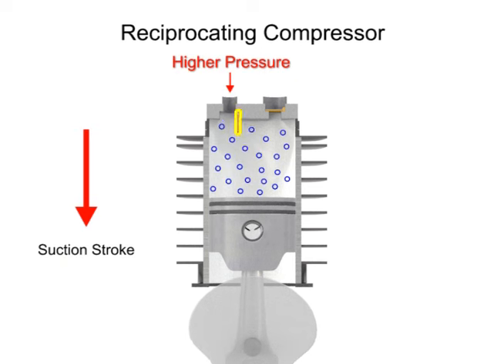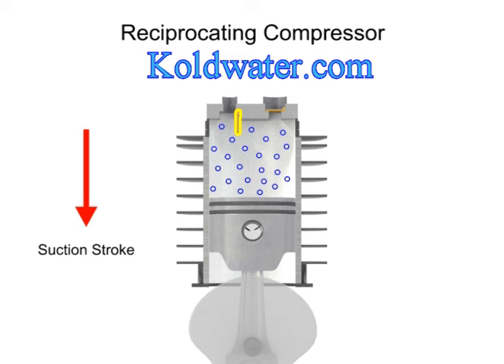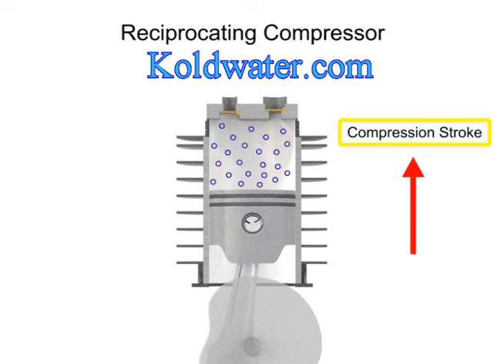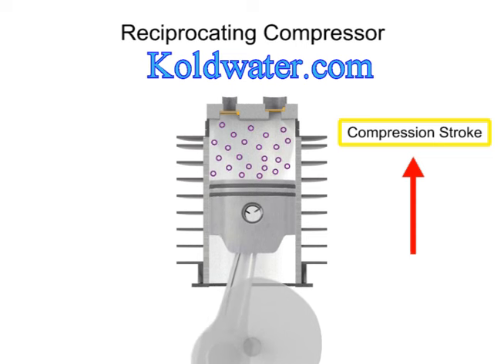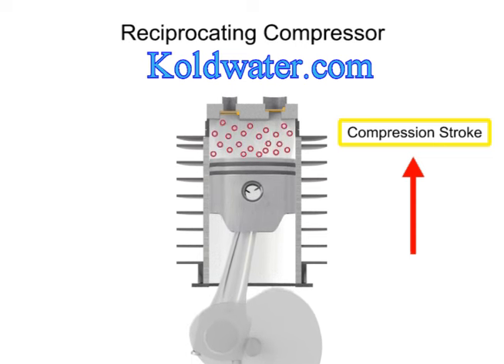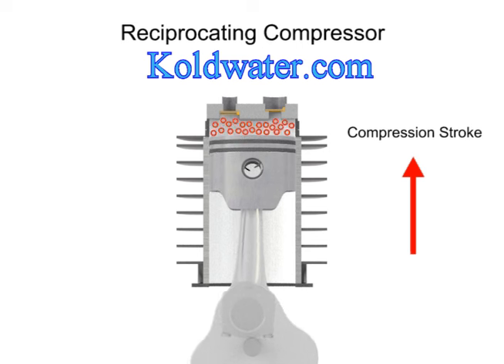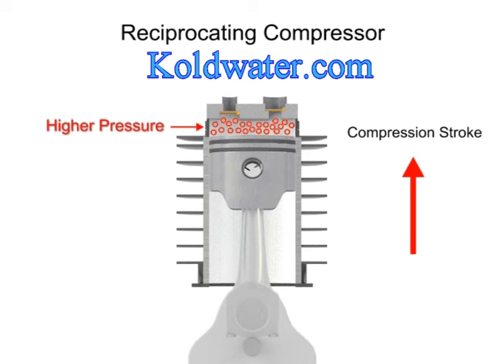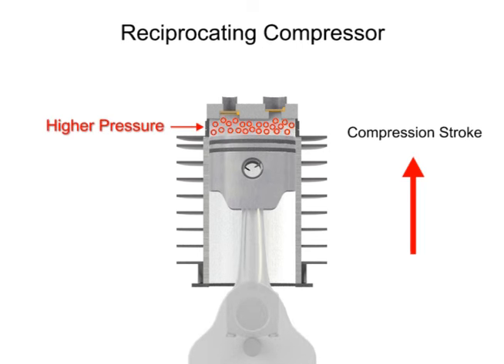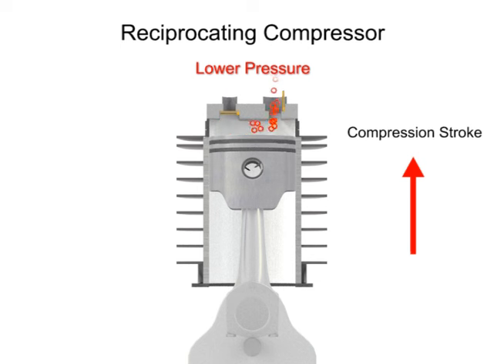This allows the higher-pressure outside air to push open the inlet valve and allow more air into the cylinder. As the piston begins its upward compression stroke, the volume within the cylinder decreases. The decrease in volume causes the pressure to increase, which opens the outlet valve, and compressed air discharges from the cylinder.